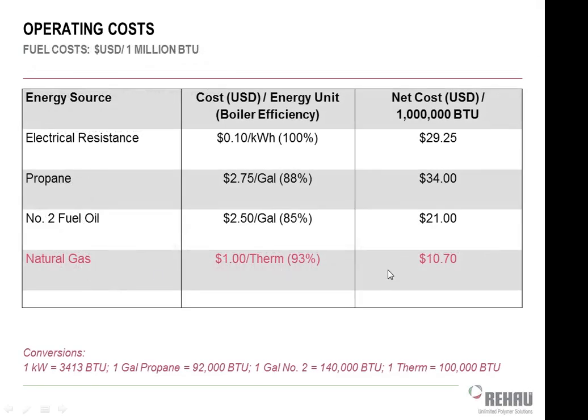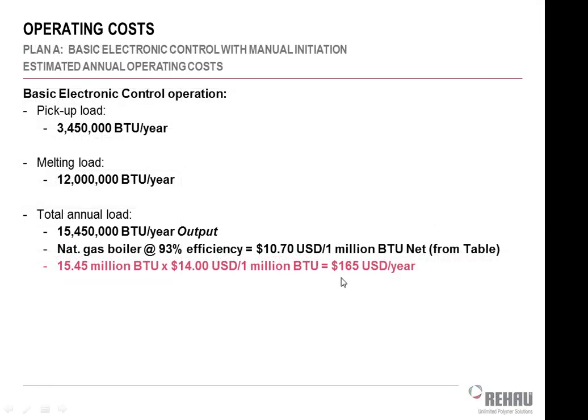And at your typical utility rate, in this case with natural gas, at this point in time we made the slide with $1 a therm. You're probably better off using 80 cents a therm nowadays, but it does go up and down. But it's basically costing you $165 a year. If the fuel rate was less, maybe it'd cost you 100. If it's more, it costs you 200. It does not cost a lot to operate one of these class 1 snowmelt systems residentially. And if you're buying a boiler anyway for your space heating needs, you don't need to upsize the boiler.